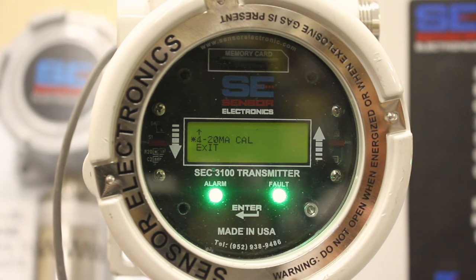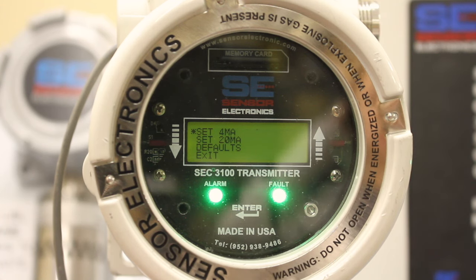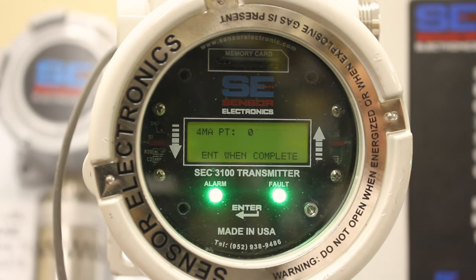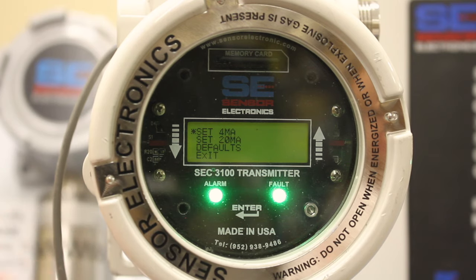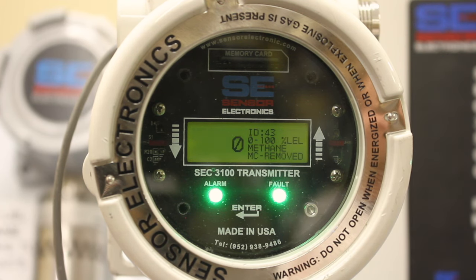4 to 20 milliamp calibration. In this menu, you're allowed to set your 4 milliamps, and if you're not getting the correct reading, if you're monitoring it back at a PLC or something, the analog output of the sensor allows you to raise and lower the 4 milliamp or the 0 reading, as well as the full scale in this menu structure. Typically it's not often used either. And then the last one is exit. So that's all the menus that are resident in the SEC 3100 transmitter.